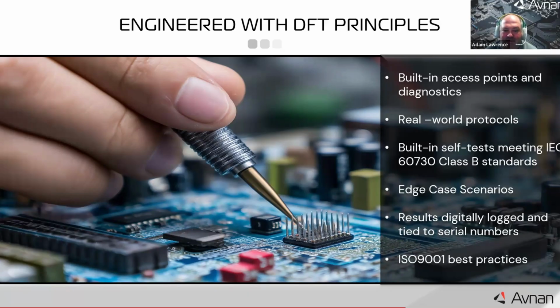Each board is engineered with design for test principles to enable maximum coverage in minimal time. Examples of this include using built-in access points and diagnostics to enable fast, thorough validation, using the controller's communication protocols, be it Modbus, RS-485, CAN, or Wi-Fi, to replicate actual operating conditions, built-in self-tests to verify sensor calibration, memory integrity, and I/O performance, meeting IEC 60730 Class B standards, simulation of edge case scenarios such as low voltage, safety trips, or sensor faults to confirm robust system response, digitally logging test data with timestamps and serial numbers for full traceability and ongoing quality improvement. This disciplined process minimizes escapes, strengthens reliability, and aligns with ISO 9001 best practices.